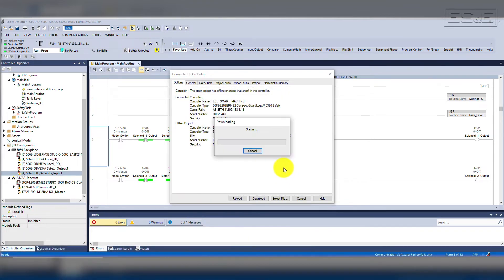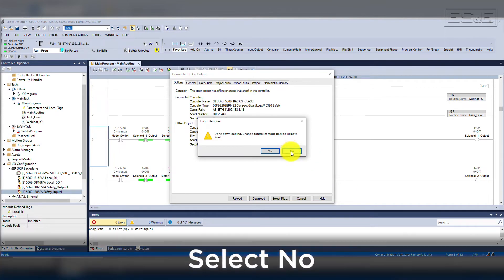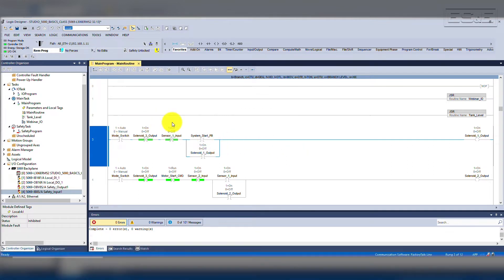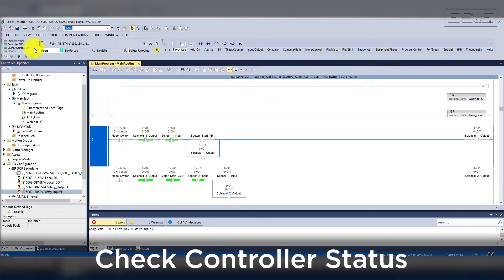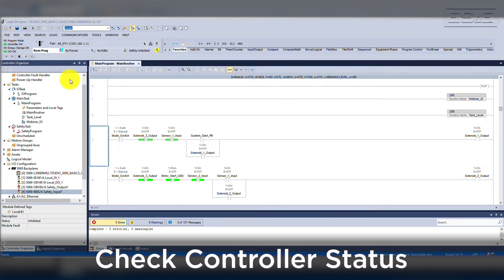Upon completion, it will ask if you want to return to remote run. I am going to hit No to show you that it stays blue and remains in program mode. Then we will look at the controller status, which shows the IO is OK, the controller is OK, and we are in program mode. If the IO configuration was wrong, the IO indicator would turn red and potentially stop the controller.